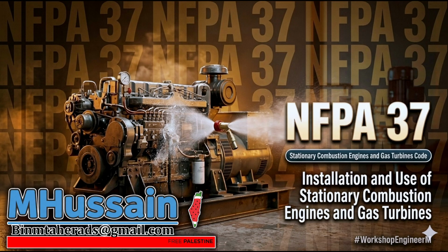Okay, so we've got the air coming in. Yeah. But we also have superheated air going out, the exhaust. The exhaust is the most acute thermal hazard in the room. The Anvil Fire blog goes into great detail on this. Yeah, they noted that exhaust manifolds run between 600 and 900 degrees Fahrenheit. 900 degrees is well above the auto-ignition temperature of most building materials. Like wood framing. If a 900-degree pipe touches a wood roof deck, it doesn't even need a spark, right?